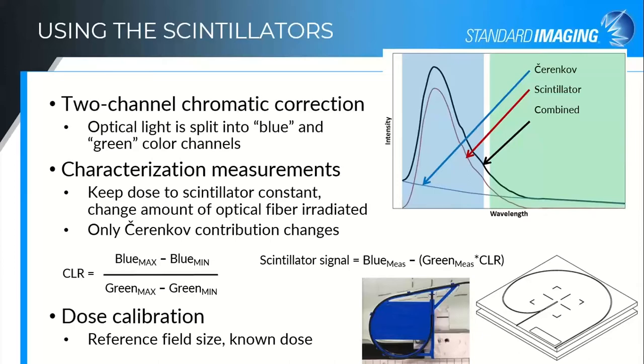The characterization measurements are designed to keep the dose to the scintillator constant while changing the amount of optical fiber that's in the field. Once positioned, you do what we call a minimum fiber measurement — with as little fiber as possible in the field — and then wrap the fiber around in one of the jigs. The blue here is the water tank jig for the W2; the larger slabs for the W1 have channels milled out. The change in Cherenkov changes only the broad-spectrum Cherenkov signal, not the scintillation signal. We look at the difference in the blue channel signal compared with the green channel signal for those two configurations to create what's called a Cherenkov light ratio — a correction factor applied to subsequent measurements to remove the Cherenkov from the blue signal based on the amount of signal in the green channel.